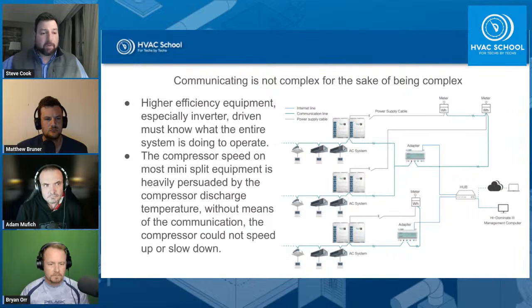You'll have a sending and receiving pulse - one component sends it to another, and they're all talking to each other, so it's the exact same. If you look at an inverter - Roman did a really good write-up earlier this year about inverters - I don't know how many people have torn apart an outdoor unit and really looked at an inverter board and seen the terminals. It doesn't matter what brand you have - the terminals that go to the inverter drive, the compressor, you'll have P, N, typically you'll have U, V, W. Those are all the same, and you're going to see nearly the same readings on those from brand to brand. As far as the inverter goes, you'll see balanced 3-phase voltage to a fan or a compressor, so whatever that is doesn't really matter - that's irrelevant.